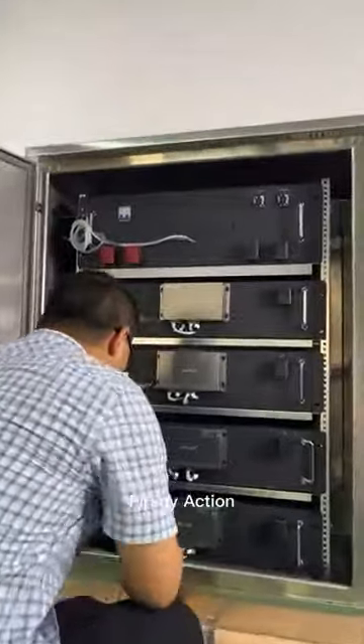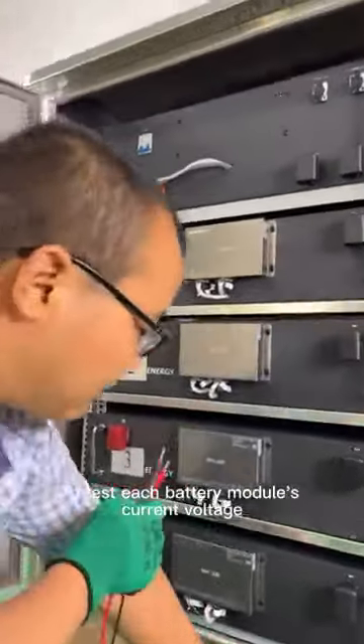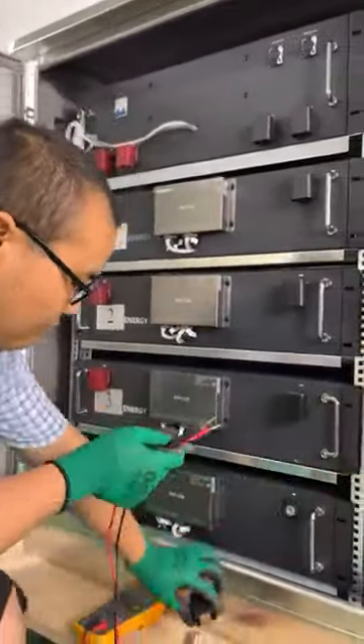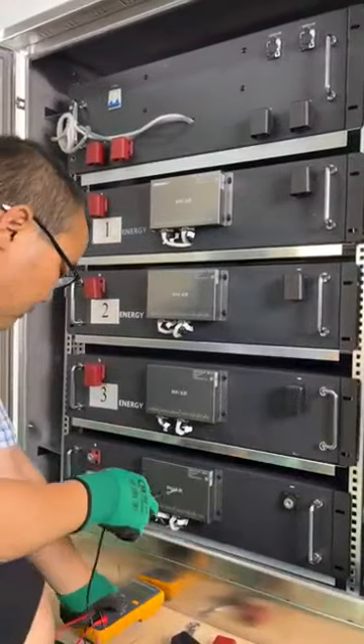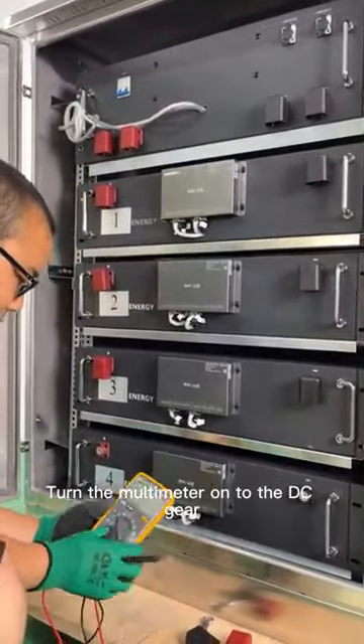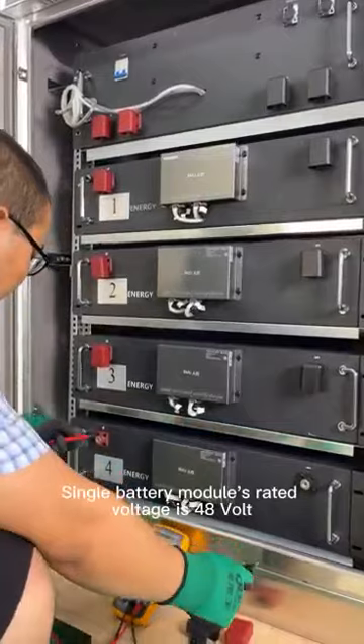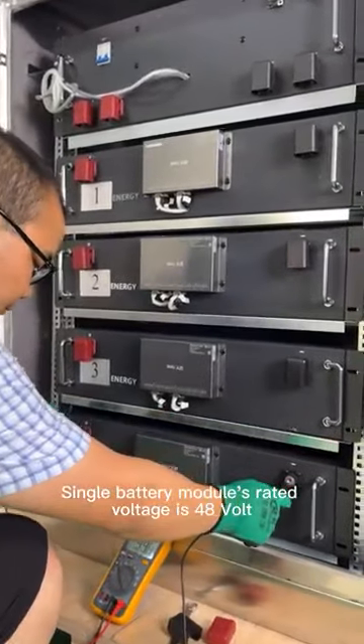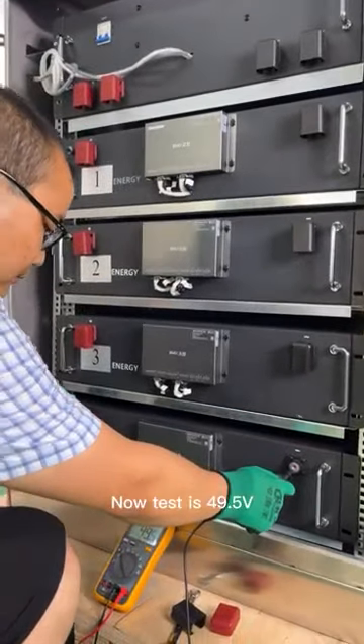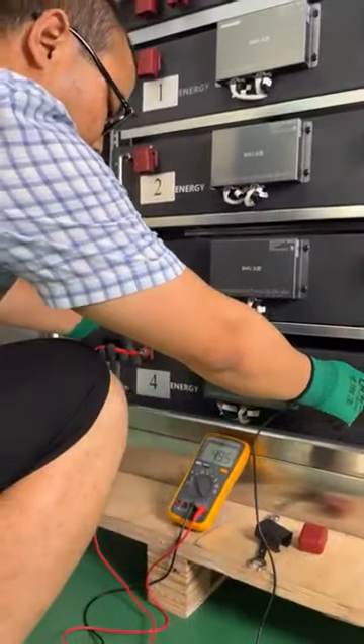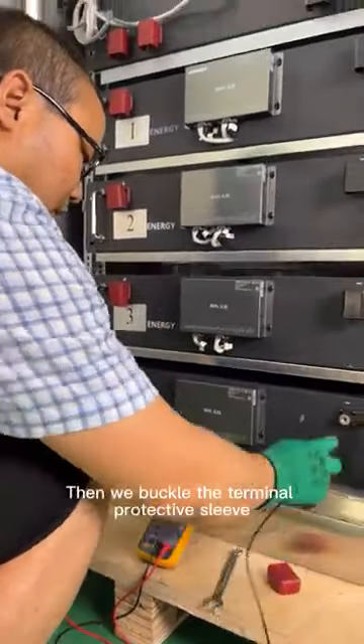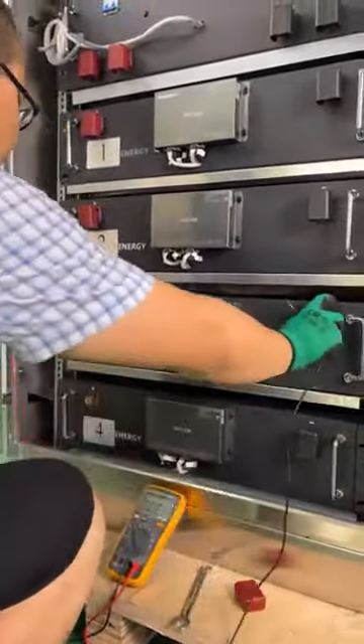Firstly, action. To test each battery module's current voltage, turn the multimeter onto the DC gear. Single battery module's rated voltage is 48 volt. Now test is 49.5 volt. Then we buckle the terminal protective sleeve.